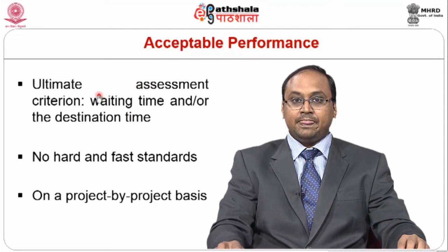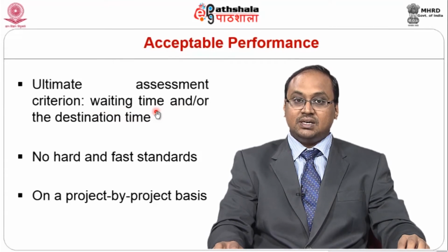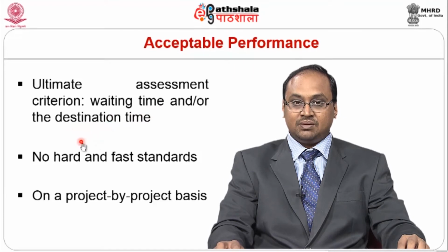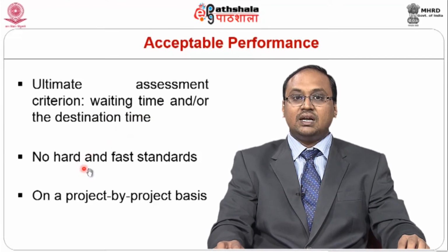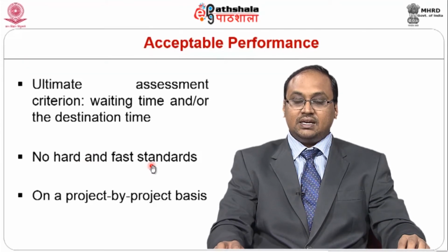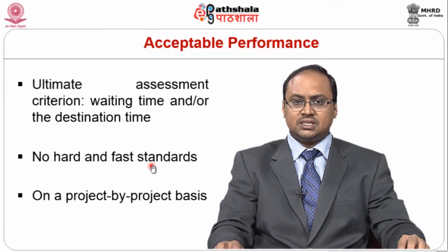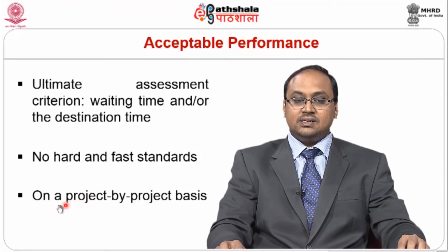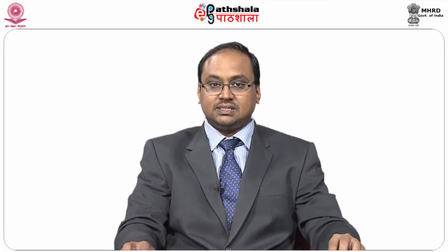Acceptable performance: the ultimate assessment criterion is waiting time and/or destination time. Waiting time is the number of seconds or minutes that the occupants have to wait in the lobbies or corridors. Destination time is how long it takes for the user to reach the destination floor from the assigned floor. There are no hard and fast standards for designing elevators for high-rise buildings, and since tall buildings are ambitious projects, design usually varies on a project-by-project basis.